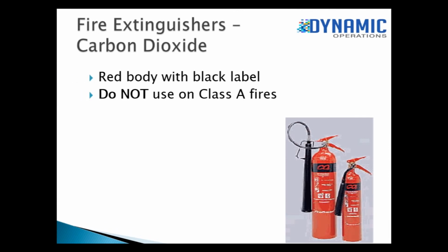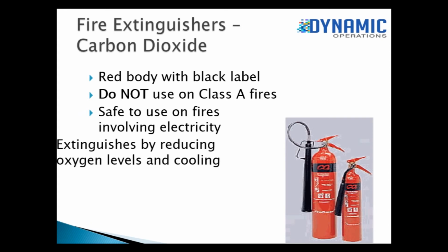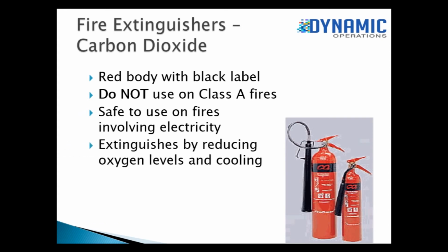And carbon dioxide, red body, black label. Do not use on Class A fires. This is gas under pressure and you will blow any burning materials all over the place. Safe to use on fires involving electricity. It extinguishes by reducing oxygen levels and cooling.